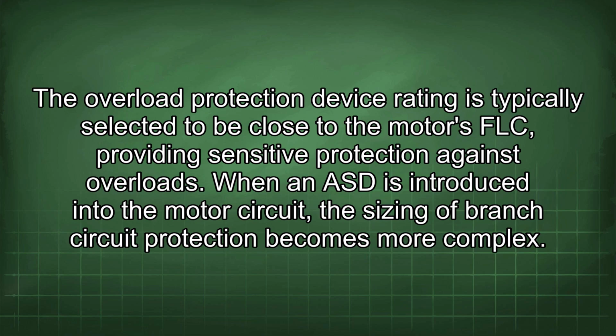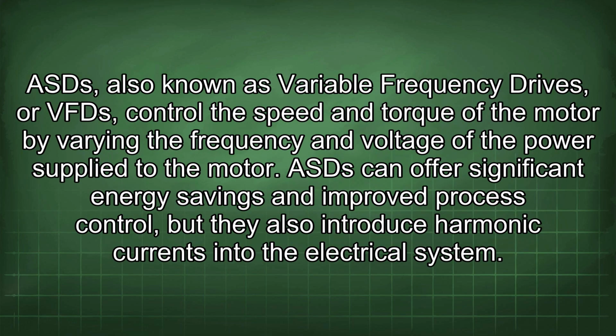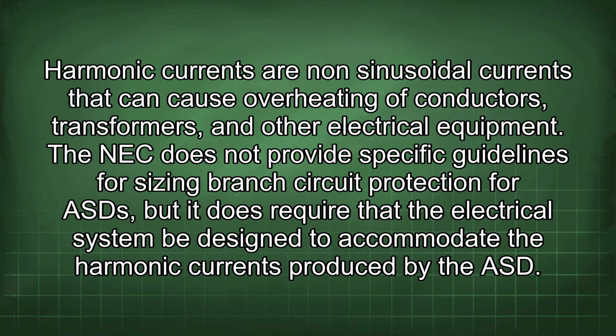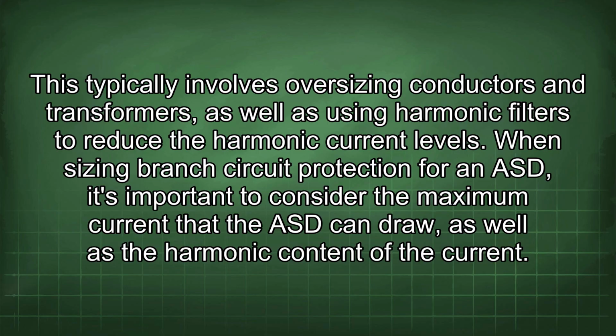When an ASD is introduced into the motor circuit, the sizing of branch circuit protection becomes more complex. ASDs, also known as variable frequency drives, or VFDs, control the speed and torque of the motor by varying the frequency and voltage of the power supplied to the motor. ASDs can offer significant energy savings and improve process control, but they also introduce harmonic currents into the electrical system. Harmonic currents are non-sinusoidal currents that can cause overheating of conductors, transformers, and other electrical equipment. The NEC does not provide specific guidelines for sizing branch circuit protection for ASD, but it does require that the electrical system be designed to accommodate the harmonic currents produced by the ASD. This typically involves oversizing conductors and transformers, as well as using harmonic filters to reduce the harmonic current levels.